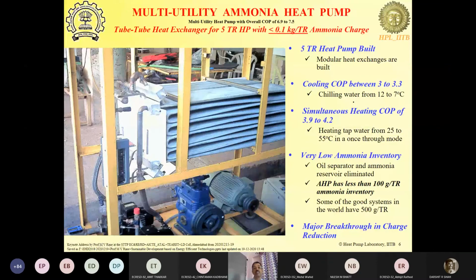The other thing about the multi-utility heat pumps was that our tube-tube heat exchangers enabled us to reduce the inventory, or the charge, of the refrigerant significantly. The unit was capable of generating a cooling effect, chilling water from 12 to 7 degrees with a COP of 3 to 3.3, and simultaneous heating was possible with a COP of 3.9 to 4.2, while water was heated in a single pass from 25 degrees to 55 degrees centigrade. And this was possible with a very low refrigerant charge of just 0.1 kg per ton.